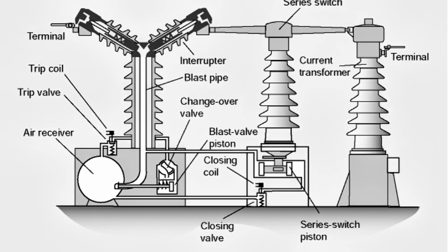This design is particularly useful in applications where the arc is highly unstable and requires a strong and directed air blast to extinguish it. In the radial blast type, the compressed air is directed radially outward from the center of the arc, which helps to rapidly cool the arc and increase its resistance. This rapid cooling and increase in resistance ultimately lead to arc extinction.